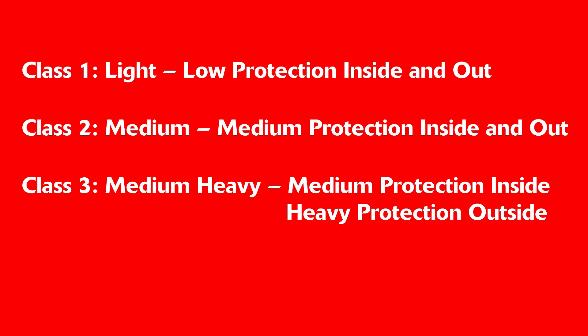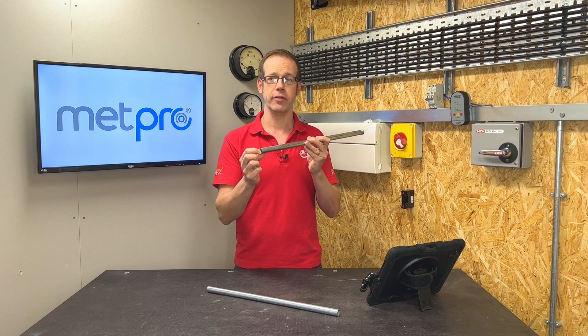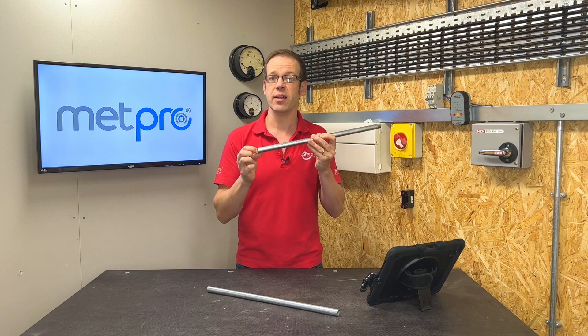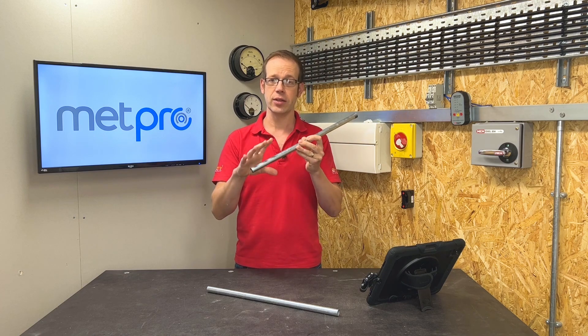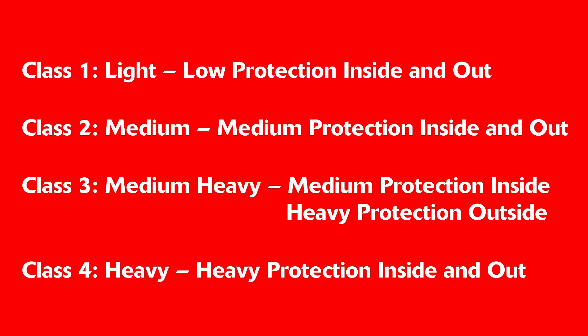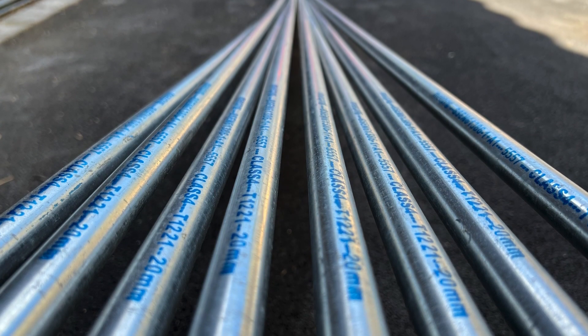So stoved enamel or electroplating offers medium protection on the inside of the conduit, and perhaps something like sherardizing offers high protection on the outside. Class 4 is then Heavy Protection, which consists of high protection both inside and out — for example, by the use of hot dipped zinc coating or sherardizing.